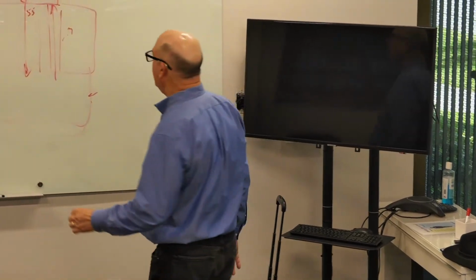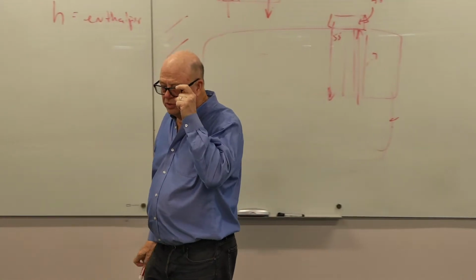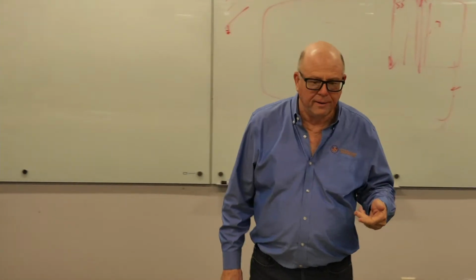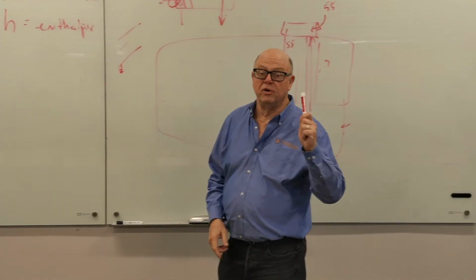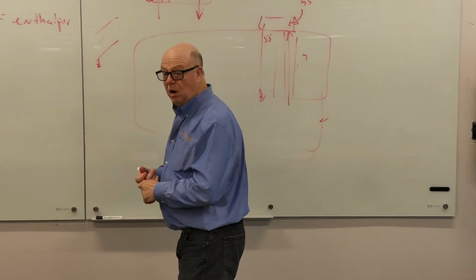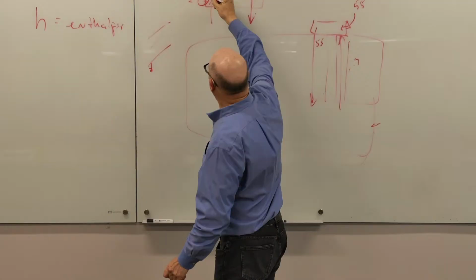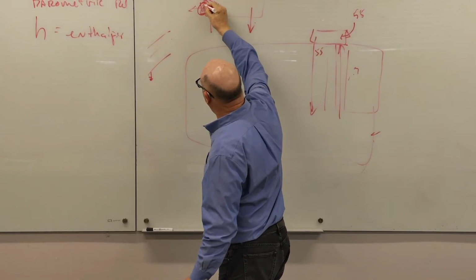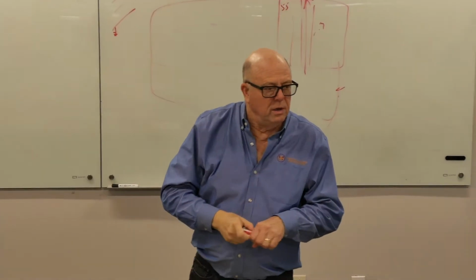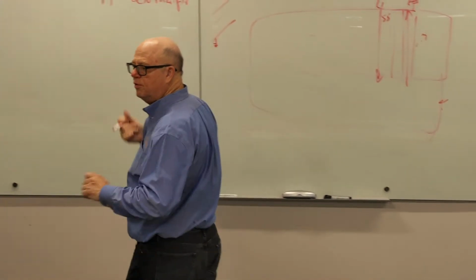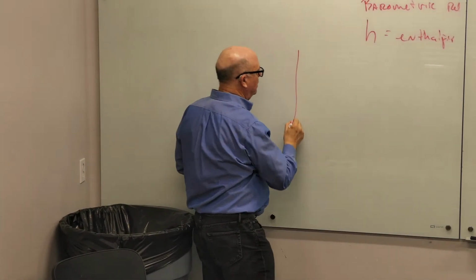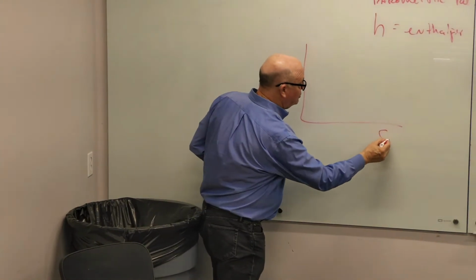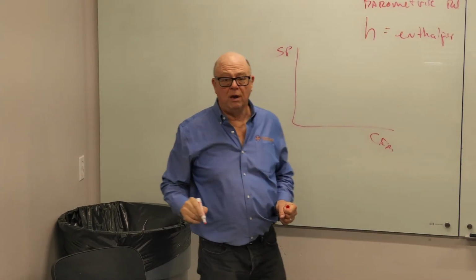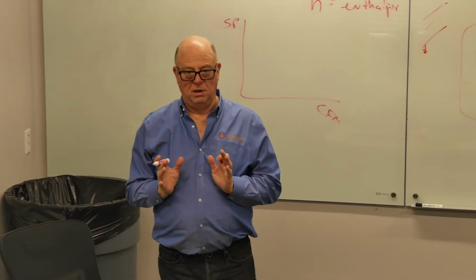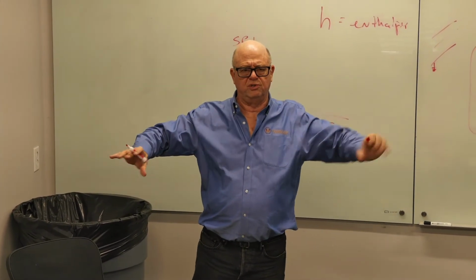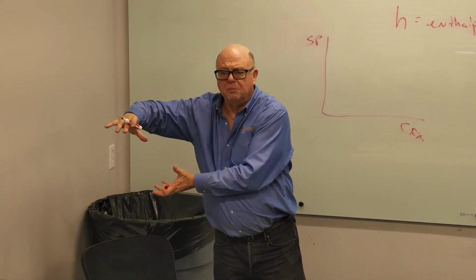So in 1991, Jim Holman, who was a sales engineer over in the office, and I came up with the first centrifugal power exhaust fan. Before that, though, on larger units, let's say that was a 15-ton, Carrier would give you a prop fan box that you would mount right here with a prop fan in it. So prop fans are weird. I don't know if you ever thought about this or realized it, but if we draw a fan curve for a prop fan, and here's our CFM, and here's our static pressure, they have a very narrow band where they do anything. A prop fan won't overcome a ton of external resistance. You put a prop fan at the end of a long duct and it'll hardly move anything.